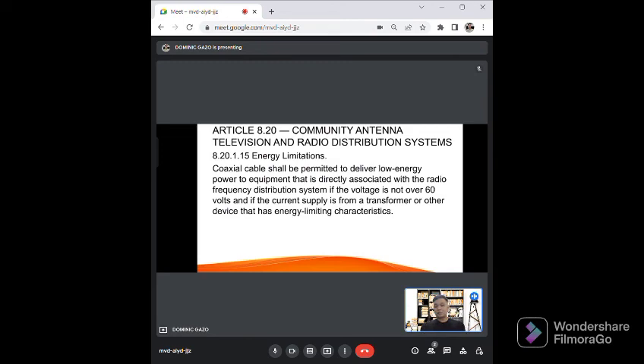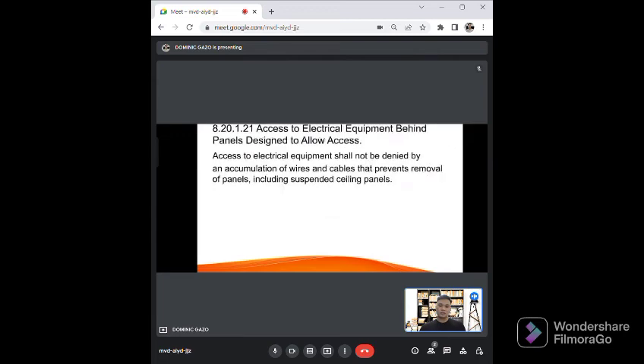For Article 8.20, Community Antenna Television and Radio Distribution Systems. For this article, for energy limitations, coaxial cables shall be permitted to deliver power to equipment that is directly associated with the radio frequency distribution system if the voltage is not over 60 volts, and the current is supplied from a transformer that has energy limiting characteristics.